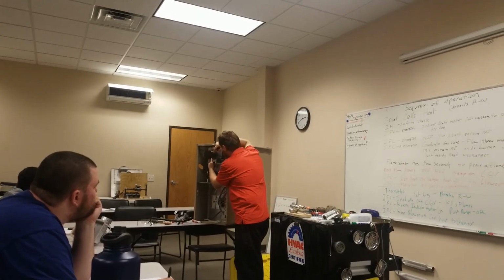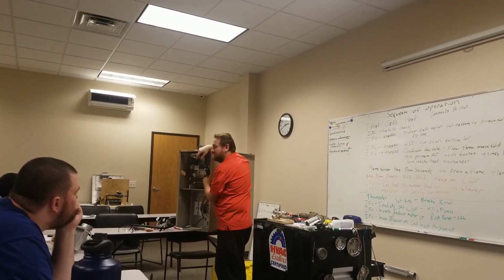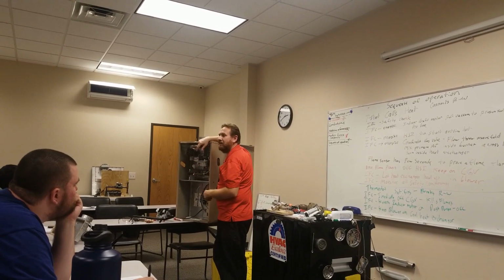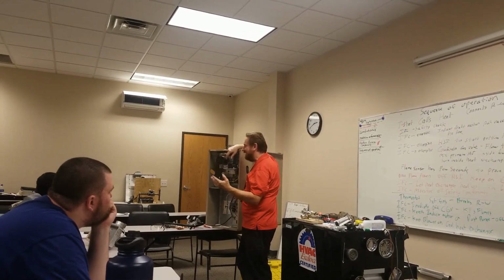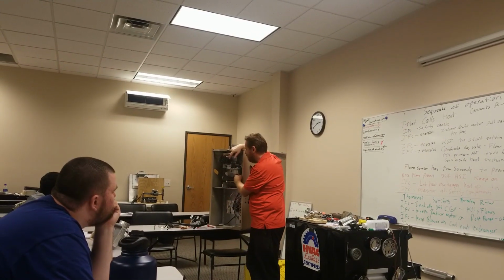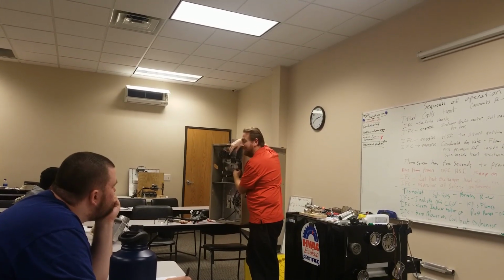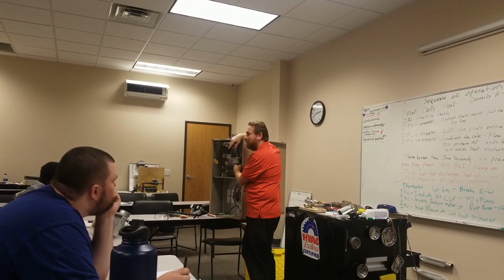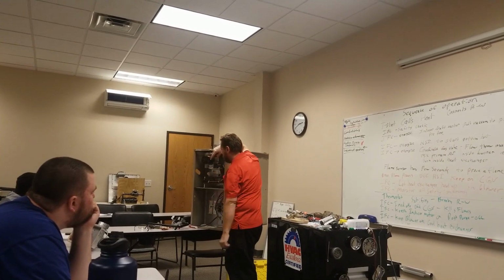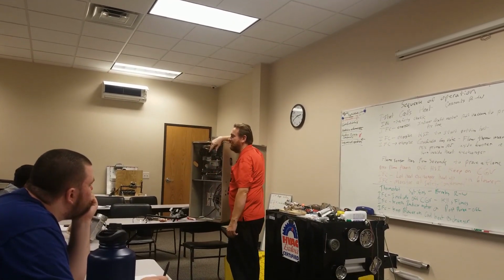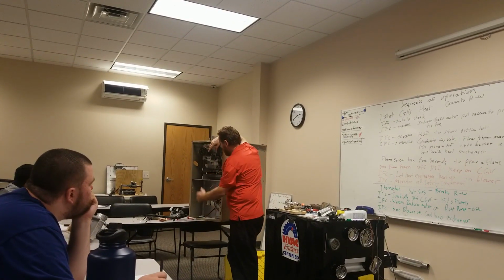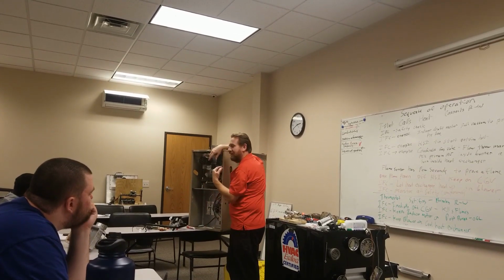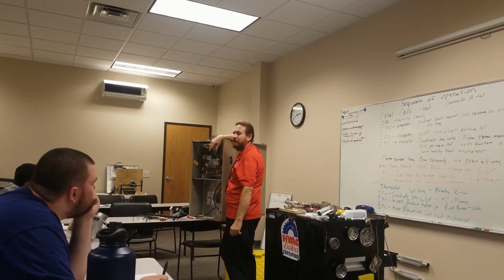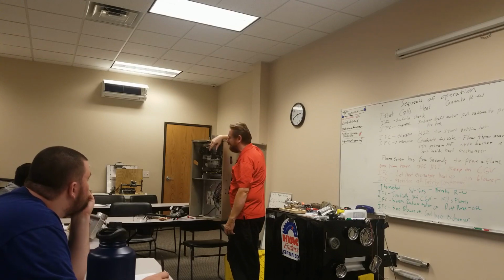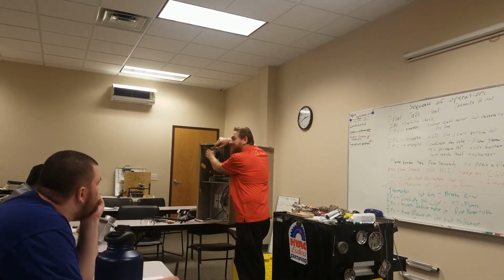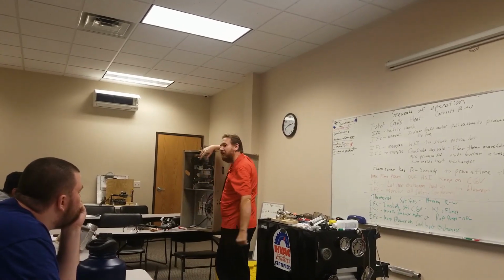On top of that, we have a high limit switch and rollout switches. If the flame rolls out, it shuts off immediately. No more standing pilot, no more wasting gas. We got a hot surface igniter that heats up. We don't have to worry about the thermocouple going bad anymore. We have a flame sensor that proves a flame through a process called flame rectification. It's almost impossible to fool. We have inshot burners that shoot it through at an angle now so that the gas is running much more efficient, saving a lot of time. And even if you have a cracked heat exchanger, because we're pulling the gas out, it's less likely to be in a carbon monoxide issue.